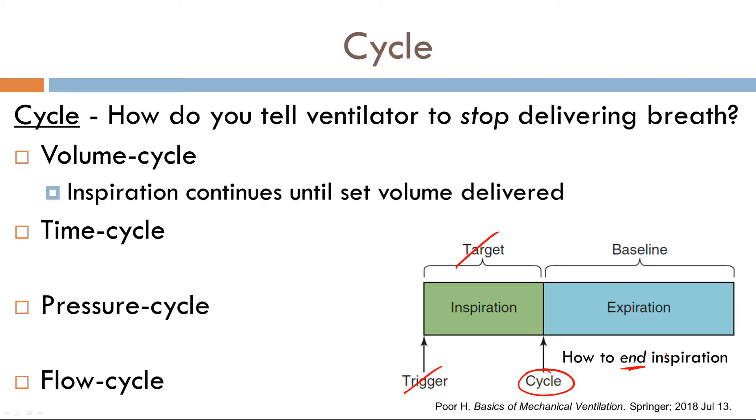What is volume cycle? Volume cycle means inspiration will continue until a set volume has been delivered. For example, if I've set it to 500 cc's, once 500 cc's has been delivered, boom, stops delivering a breath.